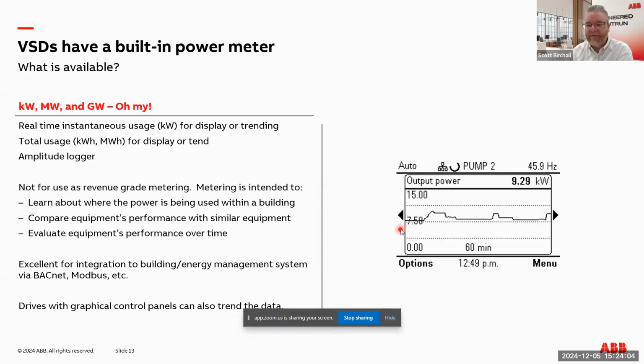One last thing: if you have a drive with a graphical control panel, you can also trend these things and set up trends on the drive. This one happens to be a 60-minute trend, but I could set it up as a 15-minute trend or a 24-hour trend. So you get little mini building automation systems right in the drive to trend and display that information, but it's just not as powerful as truly integrating it into your automation system.